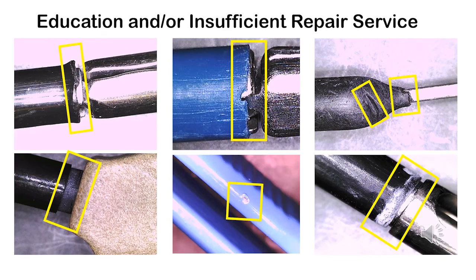Here are different pictures of bad repair services, meaning the damage was overlooked in these cases. For example, in the picture on the top left, the insulation is actually receding back, which is not good, and this was overlooked by the repair service. The top middle picture was an education issue as well as insufficient repair service, where the insulation was being pulled back but the staff didn't know that was a bad thing; they were focusing on testing the shaft but not looking at the distal end of it.